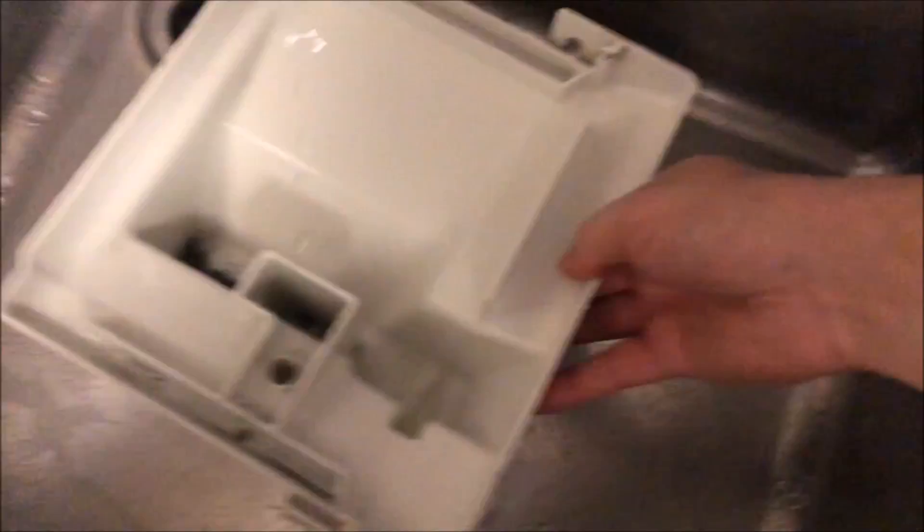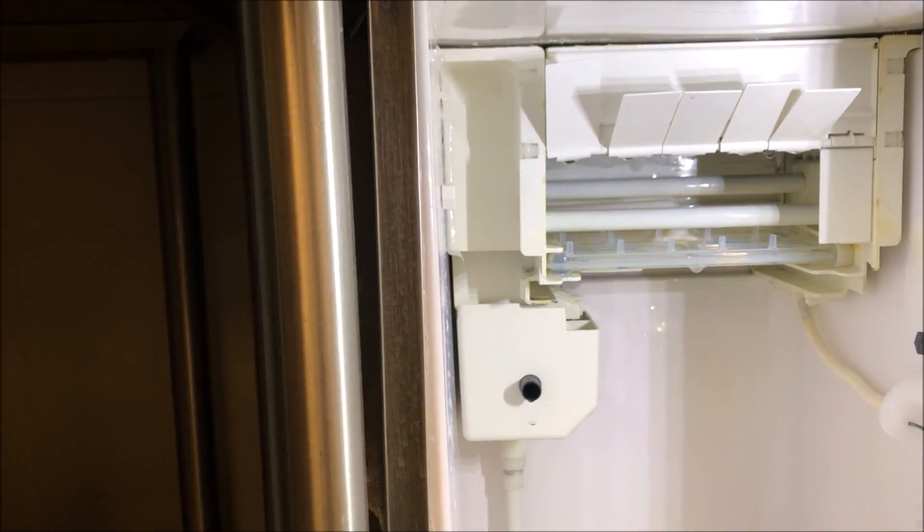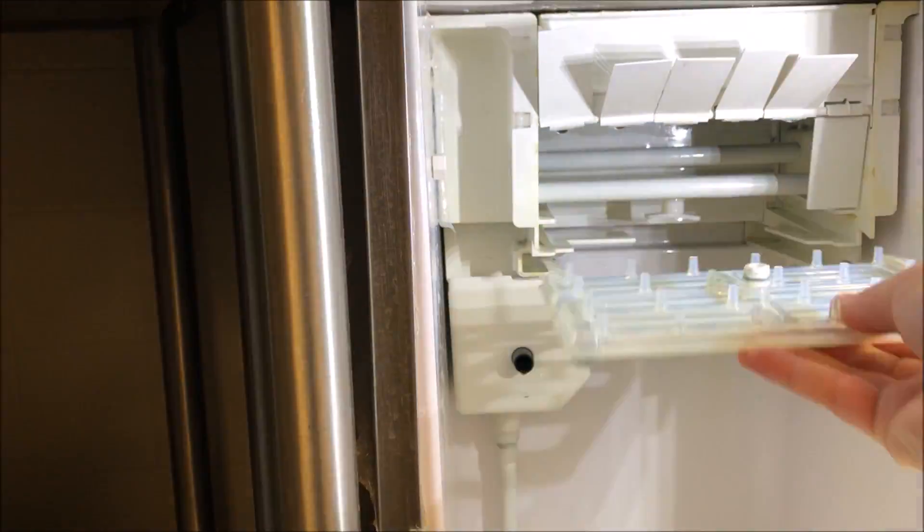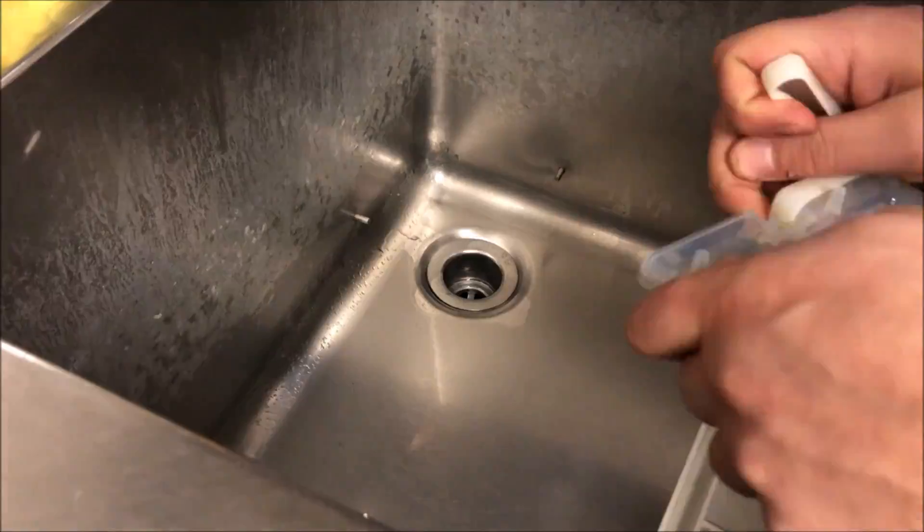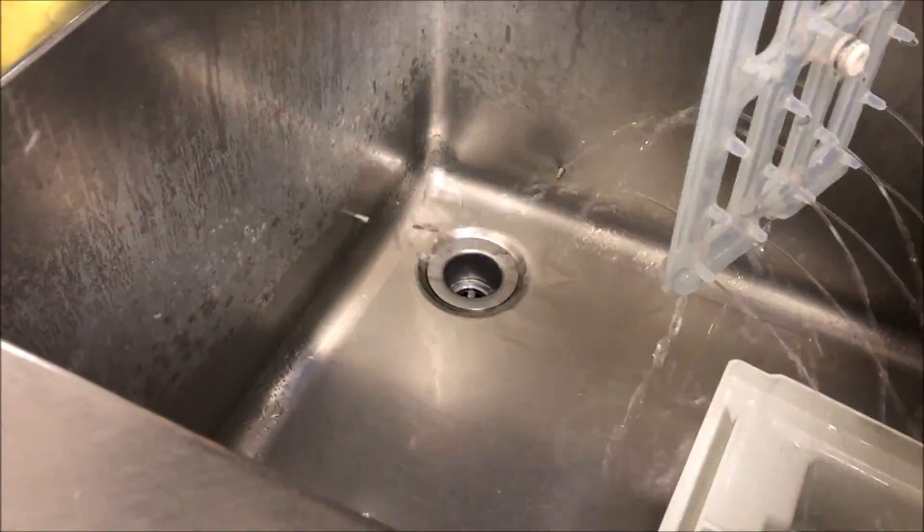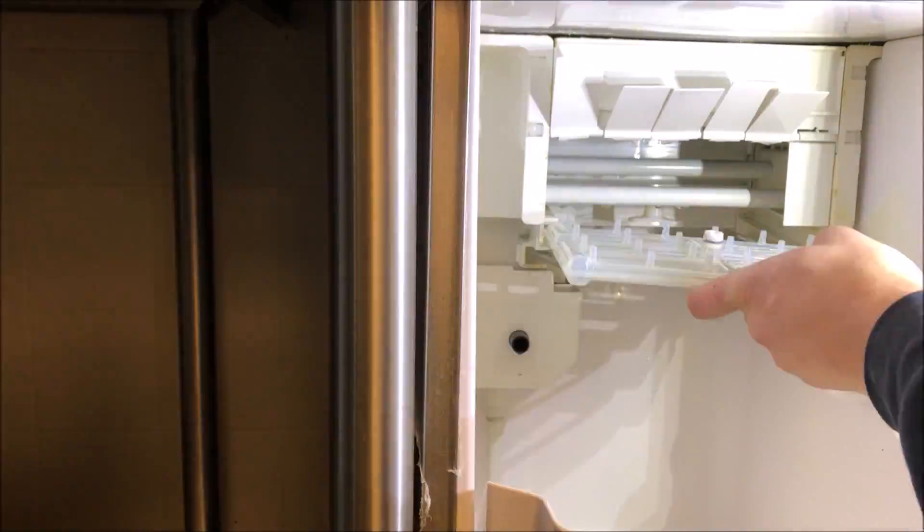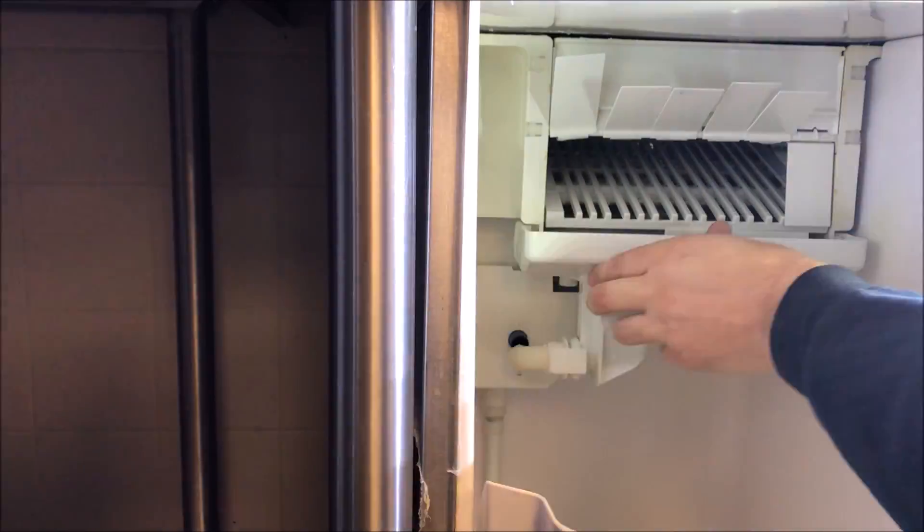One of the main reasons why this trough would leak like that is because the unit's dirty and the water is just not shooting where it should be from the pump. So let's take everything apart, let's clean it, and let's go from there.